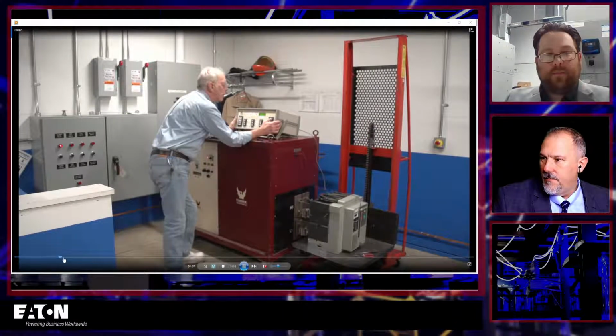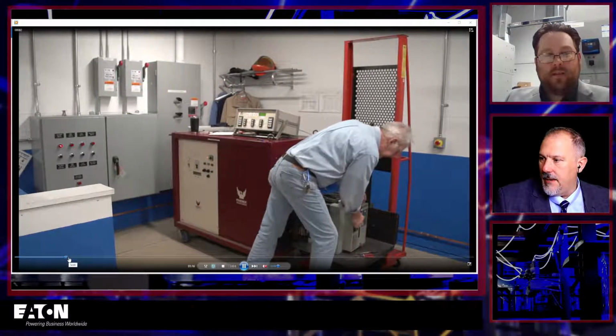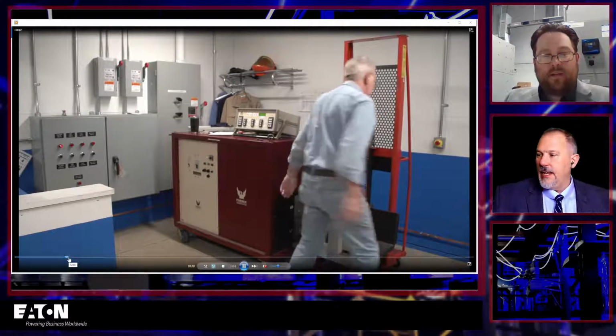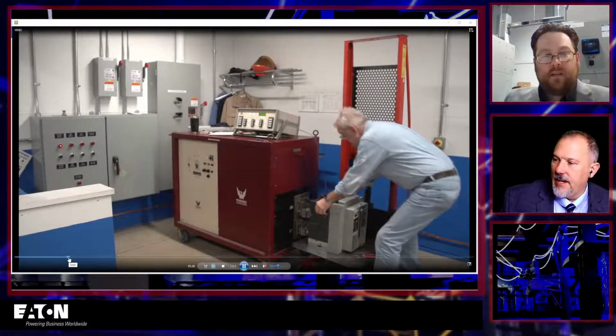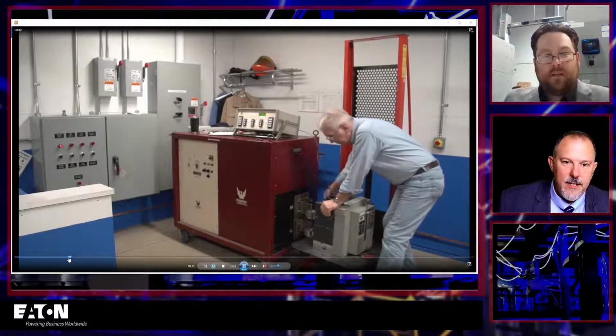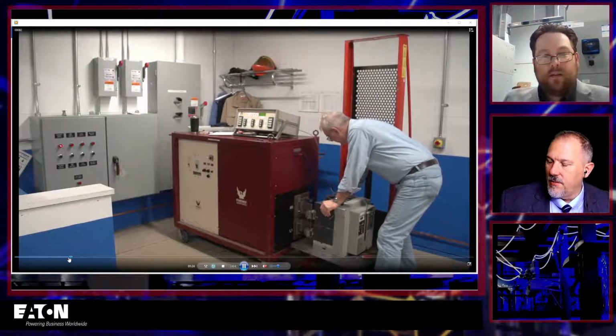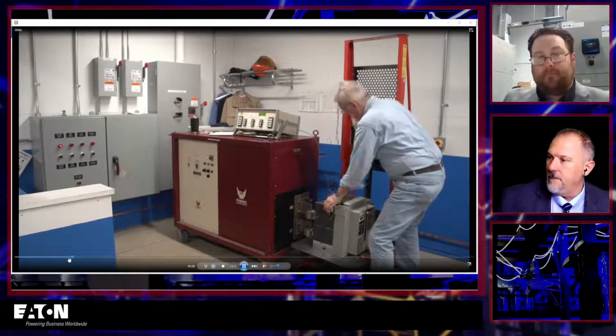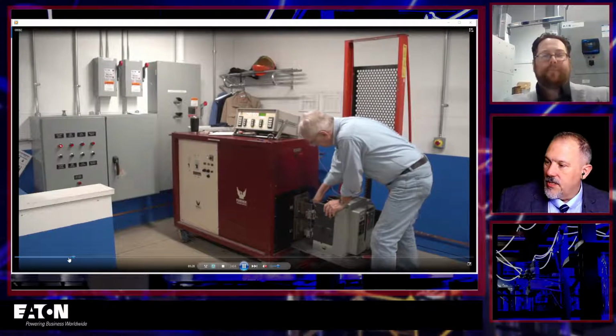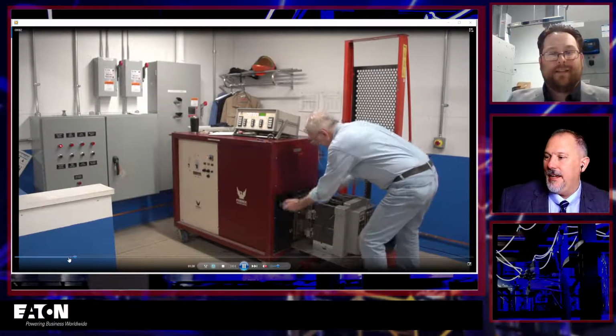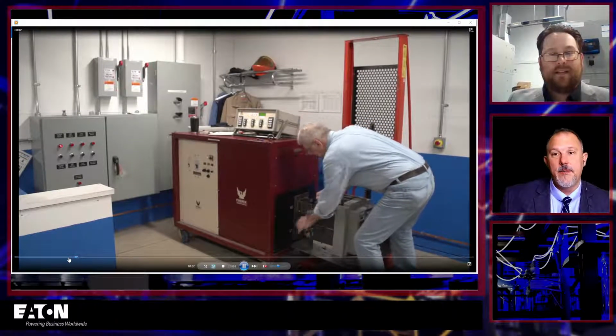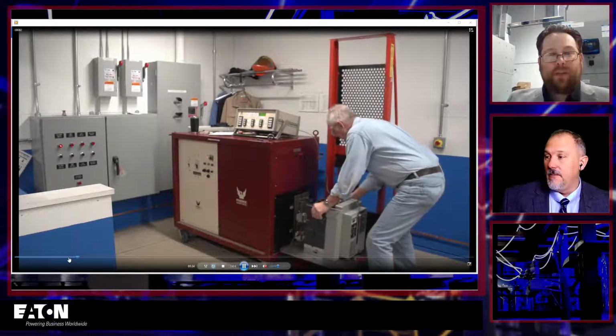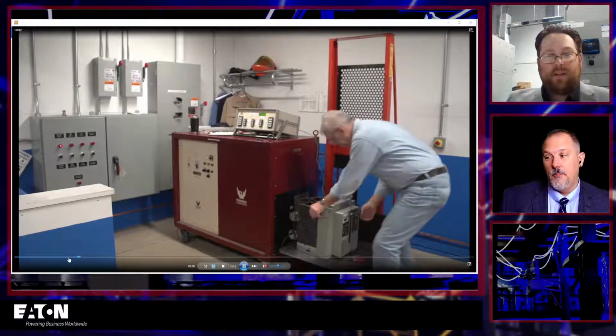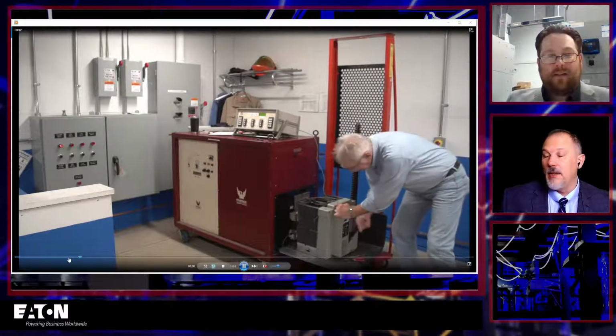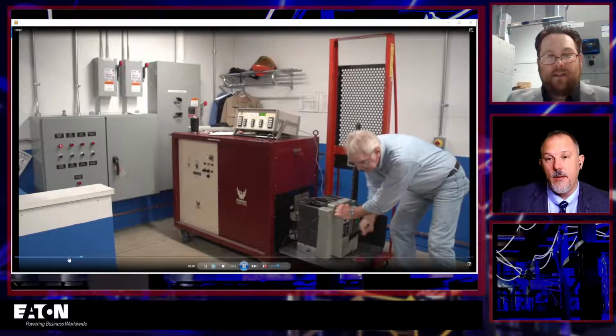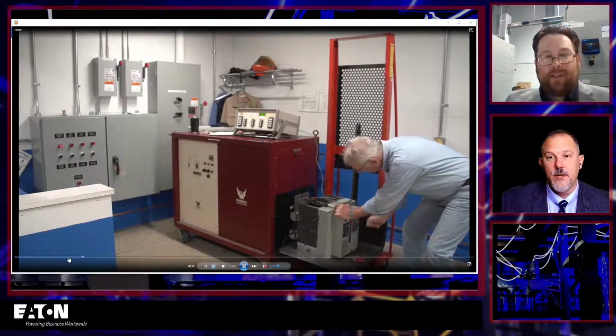I just want to find where he's actually moving that breaker. So he'll do the settings, and then he'll say, "Okay, now we're going to do a different phase of the breaker, a different pole, right?" Yep. He rearranges all of his leads. And now this equipment, look at the size of the equipment. I don't know how much that thing weighs, but then he pushes that on. Now he's not wearing any PPE. Why isn't he wearing any PPE? He doesn't have gloves on?